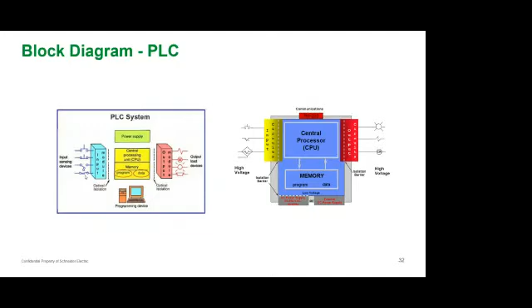Program memory is where you store the program. The engineer programs the sequence of operations, what the system has to do, and this is stored in the program memory as the sequential operation. Real-time data, like input on, input off, and other process data, is stored in the data memory. The CPU is where mathematical operations are performed, and it gives control to the controlled output through the output devices.